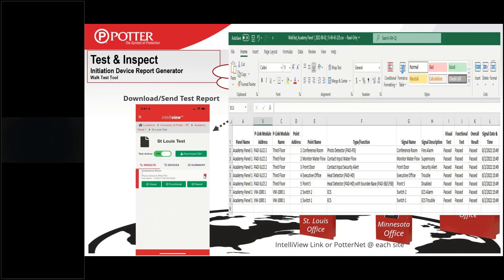The test can stay active forever. You can keep testing the system, turn off the test to go home for the night, and turn it back on in the morning. The visual, functional, and results green LEDs — you can press those. If someone painted a device, you can click and it would turn red and fail it. We're not creating NFPA 72 reports, but we're giving you a record of everything that was done on that panel, which becomes a significant part of your overall test and inspection report.